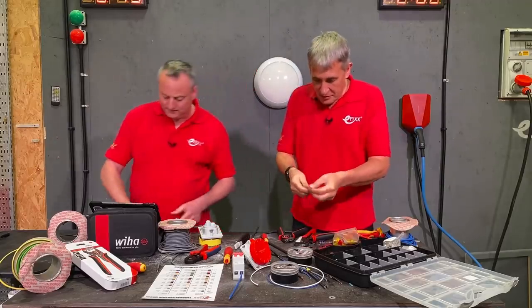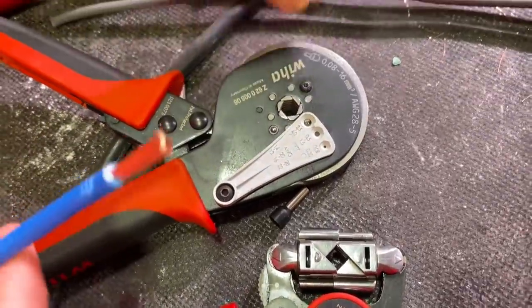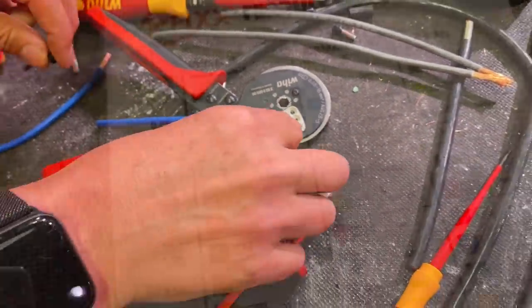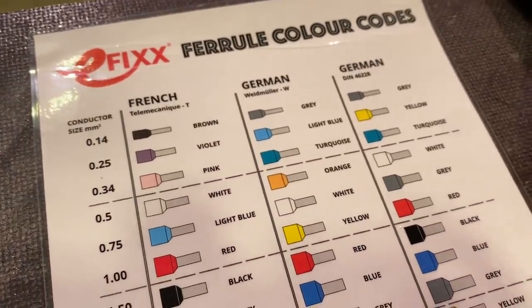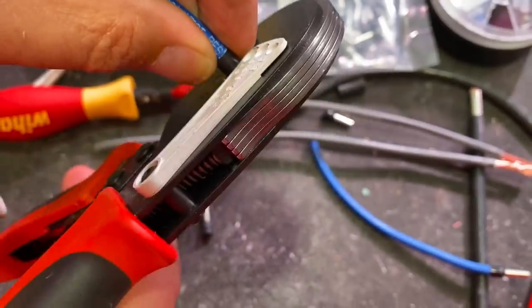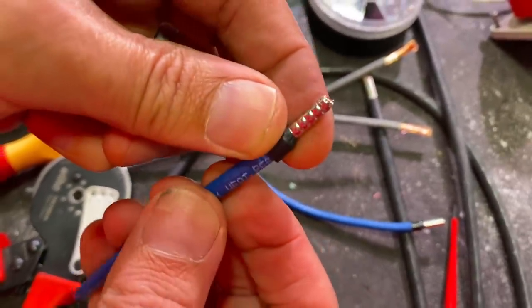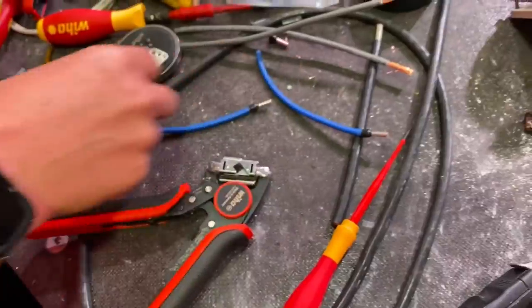Let's make a ferrule then. We'll demonstrate the difference between the two units, starting with a 6mm one — it's got a black sleeve identifying it. There are three colour code systems: two German and one French. We're currently in the Weidmüller system, and there's a mixture in use — you'll see some yellow come in shortly. In goes the ferrule — that's the pizza cutter version giving a hexagonal crimp, which is preferable when working with round terminals.